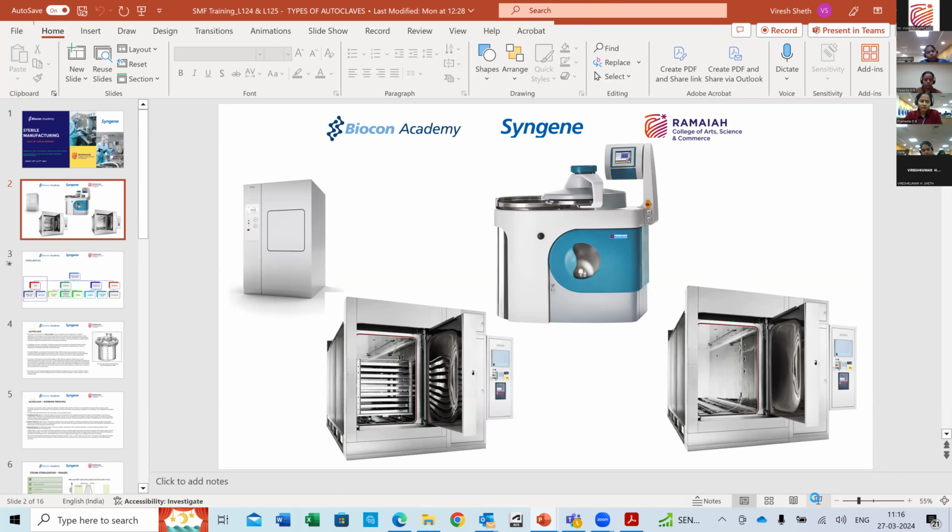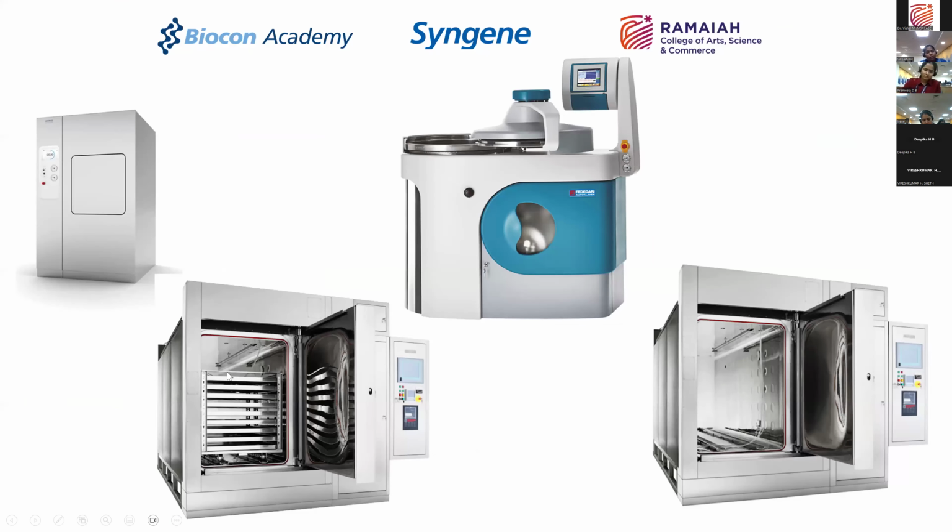Okay, let's use this as the picture. So this is an autoclave load which is there inside. So you will place your indicators maybe on the tray here, on the other end of this tray, maybe some tray in between, maybe at the bottom tray. There are some locations which you will determine.